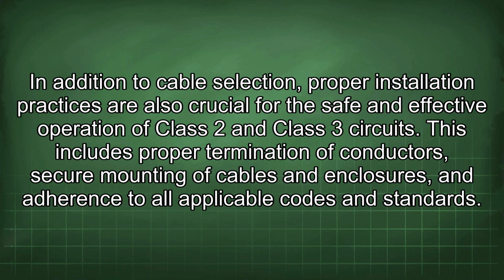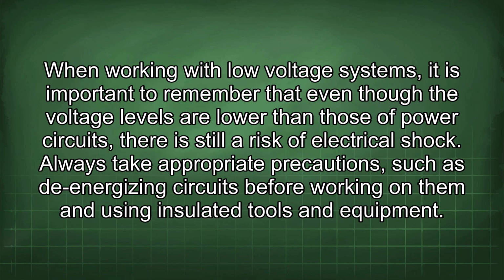In addition to cable selection, proper installation practices are also crucial for the safe and effective operation of Class 2 and Class 3 circuits. This includes proper termination of conductors, secure mounting of cables and enclosures, and adherence to all applicable codes and standards. When working with low-voltage systems, it is important to remember that even though the voltage levels are lower than those of power circuits, there is still a risk of electrical shock. Always take appropriate precautions, such as de-energizing circuits before working on them and using insulated tools and equipment.